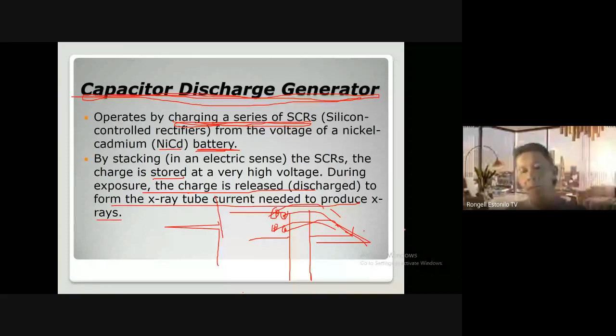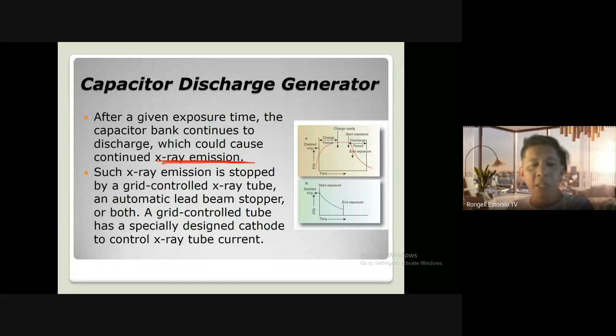So, after a given exposure time, the capacitor bank continues to discharge, which could cause continued X-ray emission. Kaya nagiging illegal siya in a way. Kasi, kahit di rin siya ginagamit, nag-i-emit siya ng X-ray, which is quite delikado. Such X-ray emission is only stopped by a grid-controlled X-ray tube, an automatic lead beam stopper, or both. So a grid-controlled tube has a specially designed cathode to control X-ray tube current.